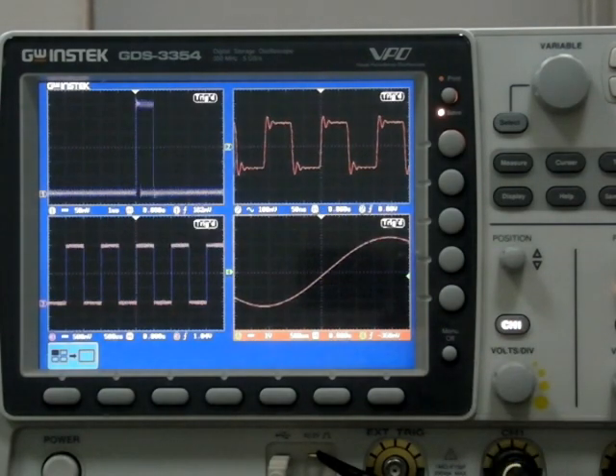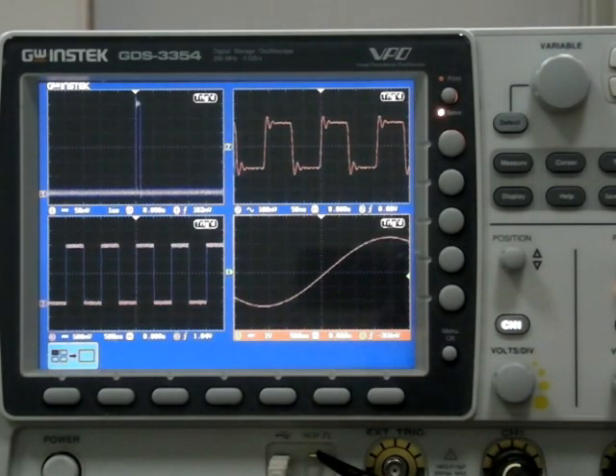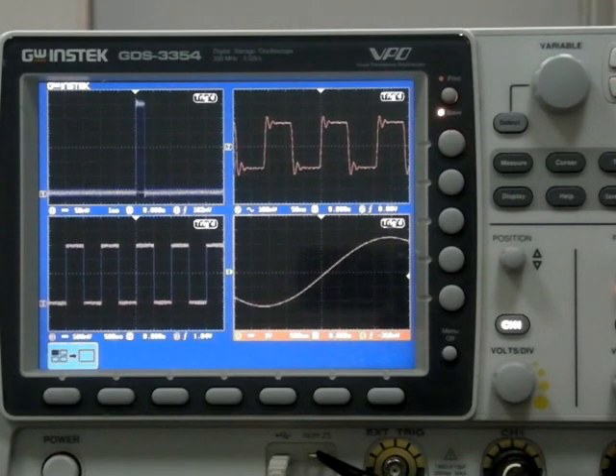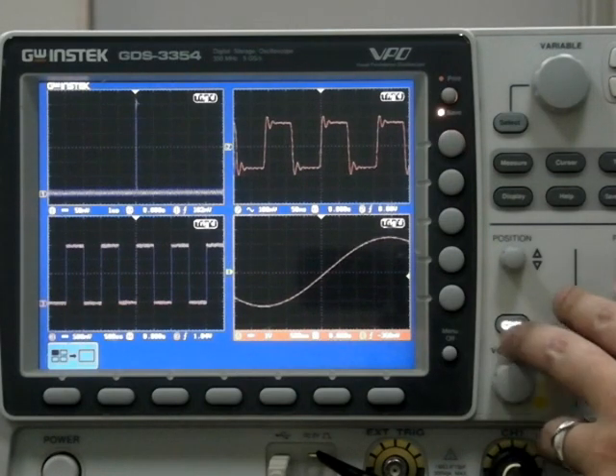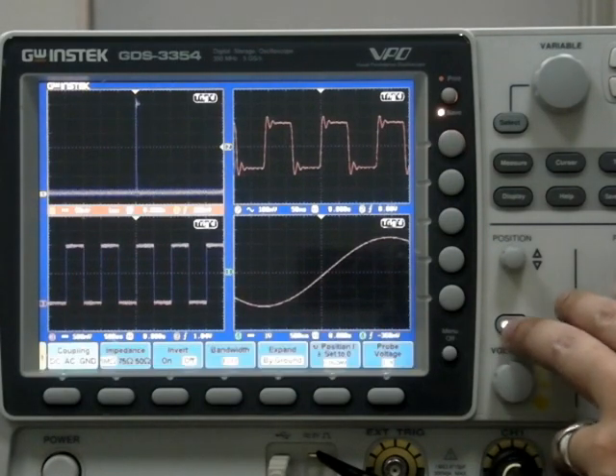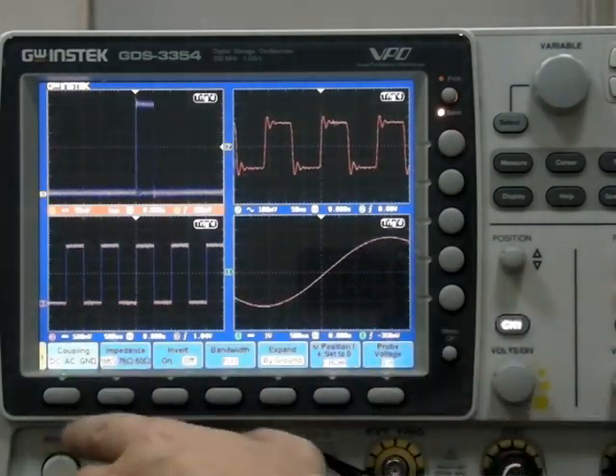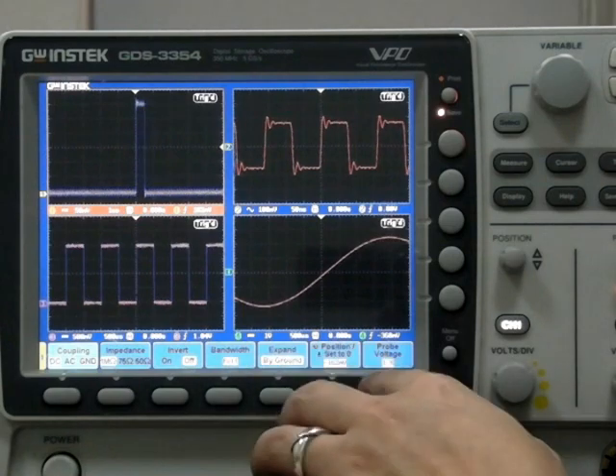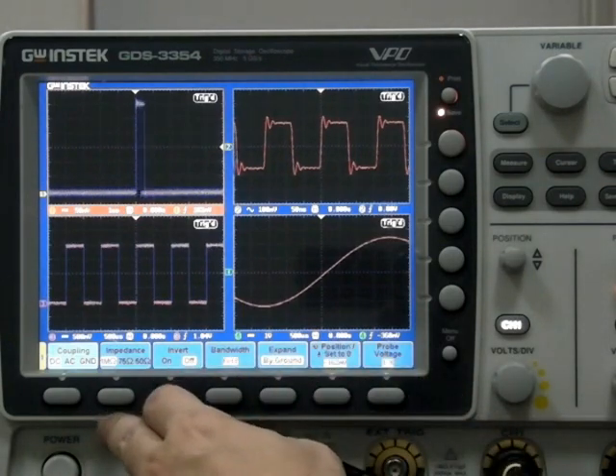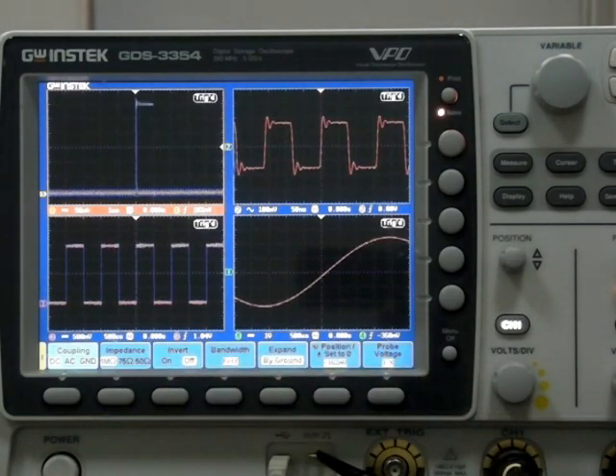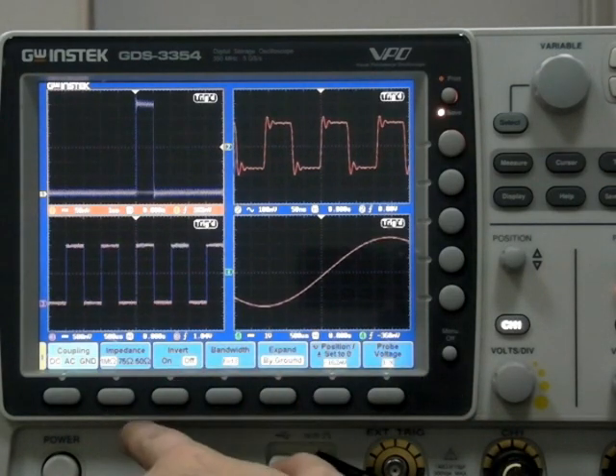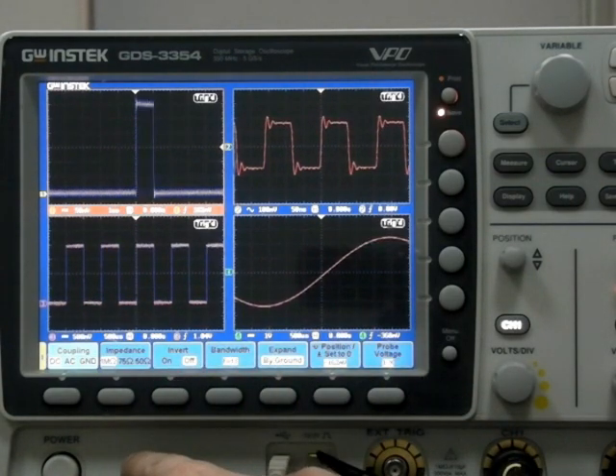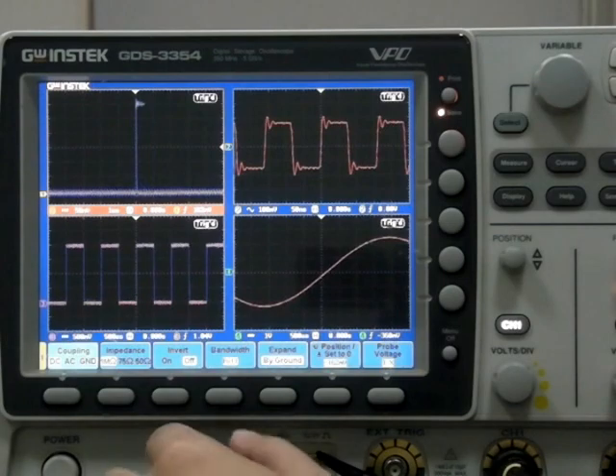Each window can be configured with independent vertical settings, trigger settings, and automatic measurements. Press the Channel 1 to Channel 4 key to set the impedance: 1M, 75, and 50 Ohm for each channel independently.